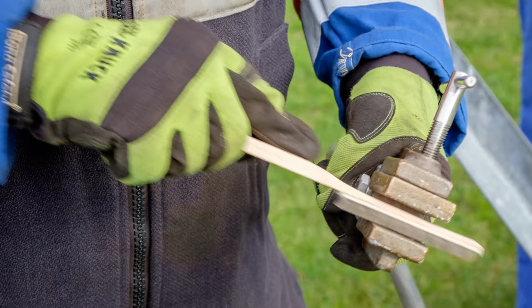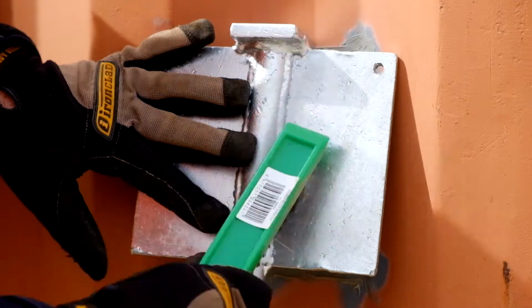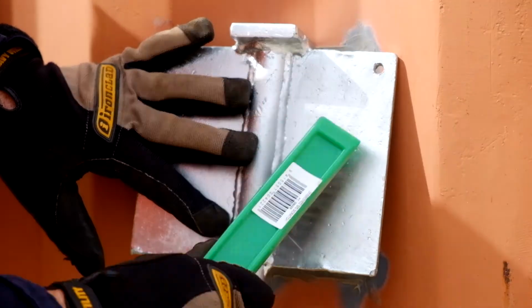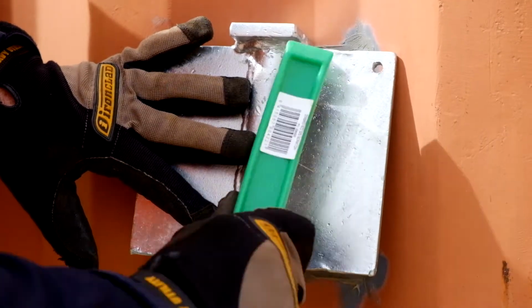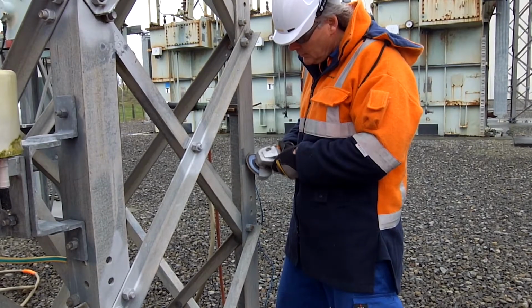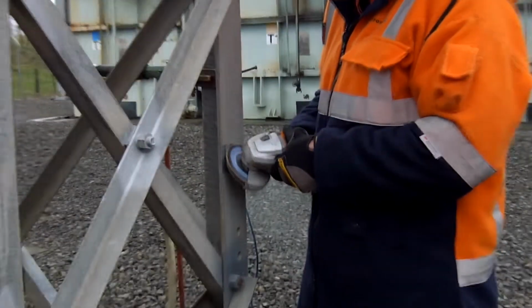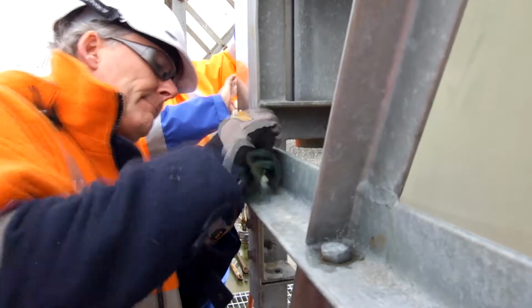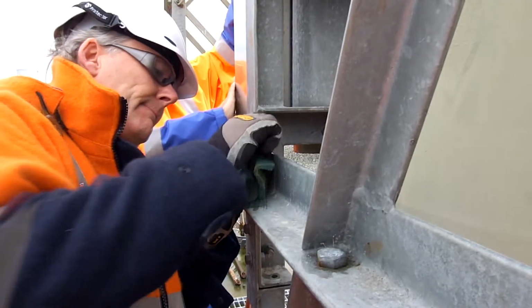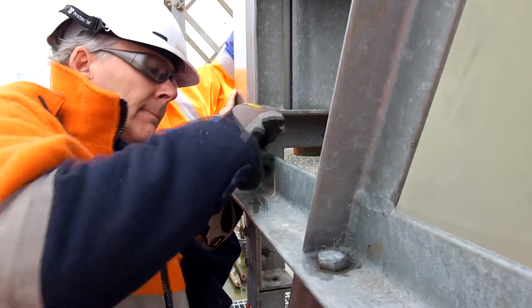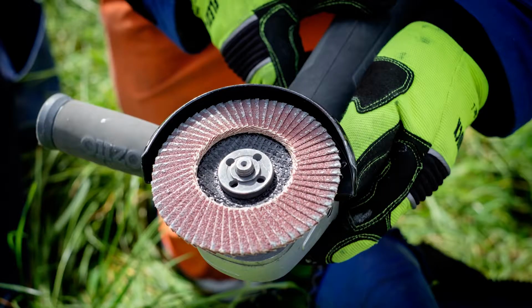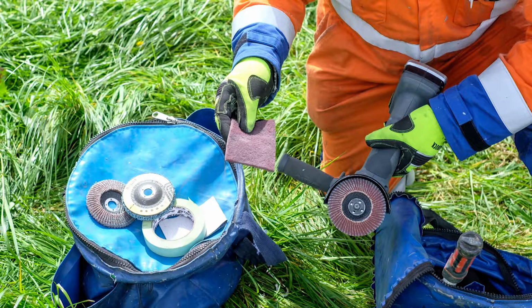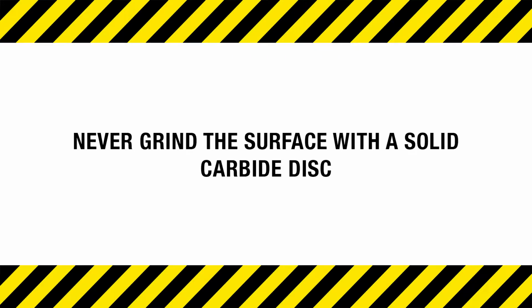Once you've cleaned the tail clamp, make sure that the surface you're attaching it to is also clean and free from paint, dirt or corrosion. Weathered galvanized steel surfaces may take a lot of effort to clean. You might be able to use a wire brush, but if that doesn't work, you need to consider using Scotch-Brite, emery paper, or even a battery-powered angle grinder with a sanding pad to get a clean surface. Never grind the surface with a solid carbide disc.